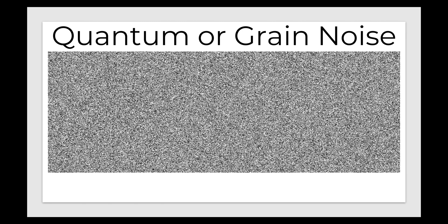There are different types of noise that we can have in an image, and in this video we're going to talk about four different kinds. In this first image, we're looking at quantum noise or grain noise. This is caused by fluctuations in the number of photons that interact with the detector from one point to another. If we expose the detector to a uniform radiation beam — say in an x-ray unit or a CT scanner — we would actually end up getting a grainy image instead of a completely uniform image. That grainy image is what we call quantum noise, and that's the source of most of the noise we see in medical imaging.